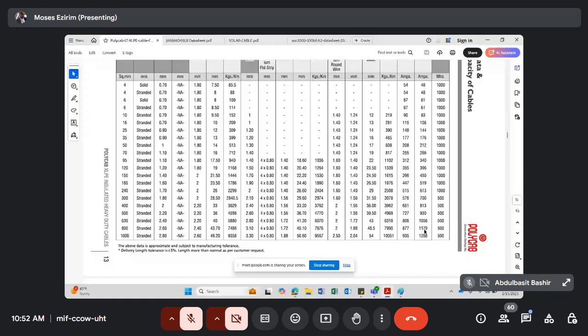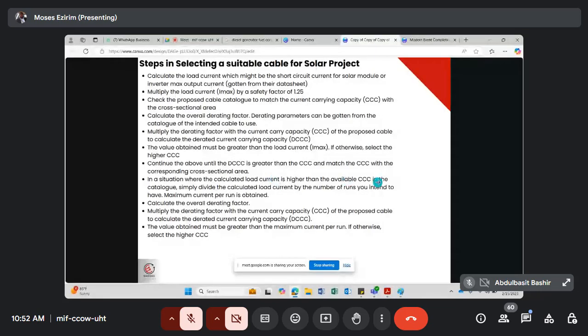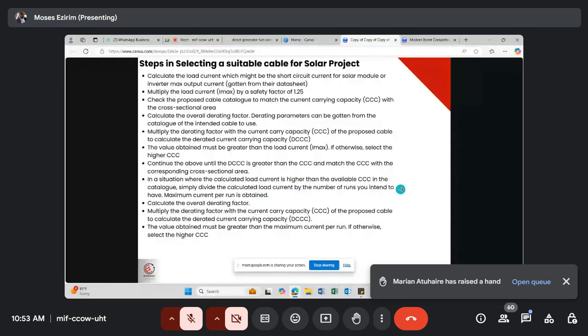What do you want to cover for this situation? What you simply do is this: in a situation where the calculated load current is higher than the available CCC in the catalog, simply divide the calculated load current by the number of runs you intend to have.